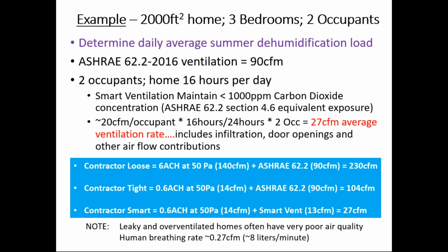So this example, though, we just want to make real that this humidity, that it's not magic, that we can determine what we need to do and then figure out what we have for doing that. So let's say we have this 2,000 square foot home, 3 bedrooms, 2 occupants. ASHRAE ventilation standard would be 90 cubic feet per minute. And if we assume 2 occupants in the house, 16 hours per day, and if we would like to maintain an indoor air quality in which carbon dioxide on average is no greater than 1,000 parts per million, and this is nominally what the ASHRAE 62.2 and the commercial building 62.1 standards are geared toward, then we would have about 20 cubic feet per minute per occupant.